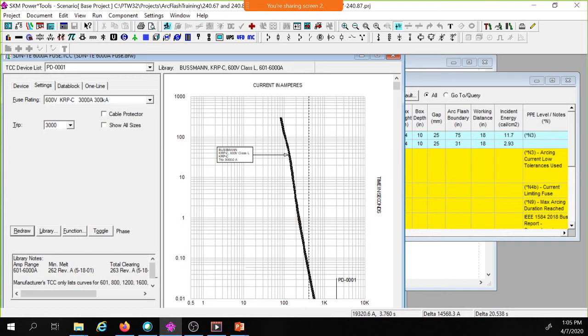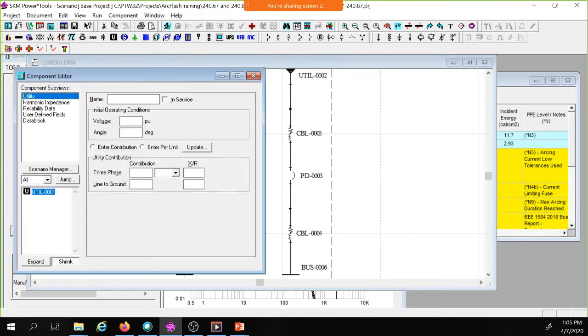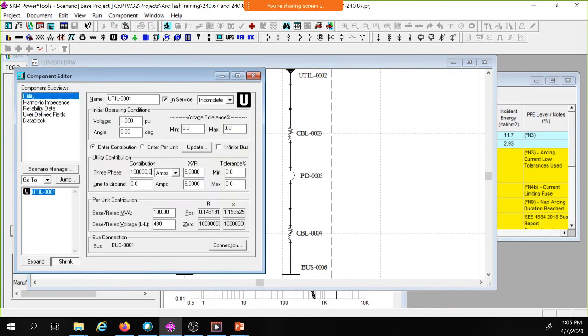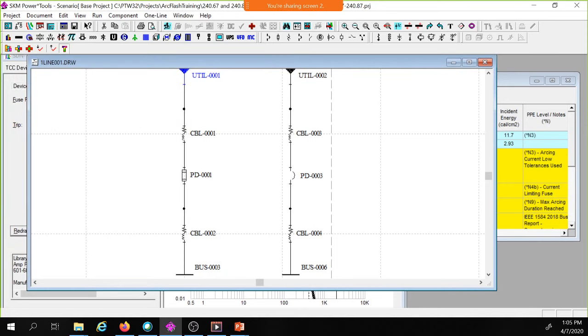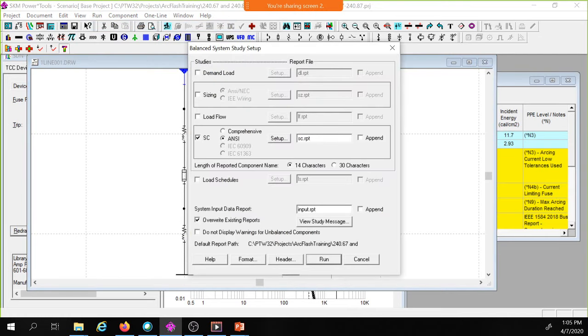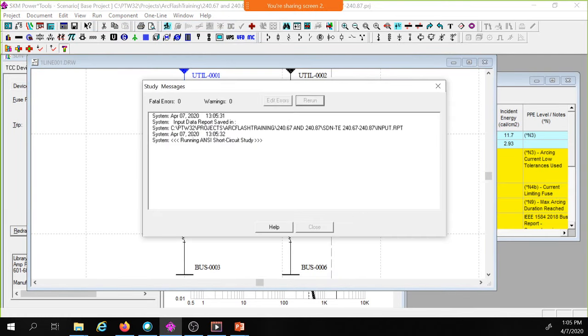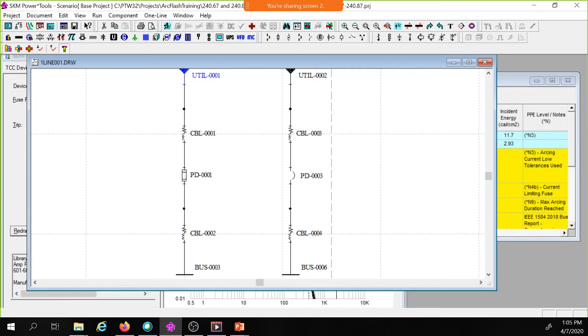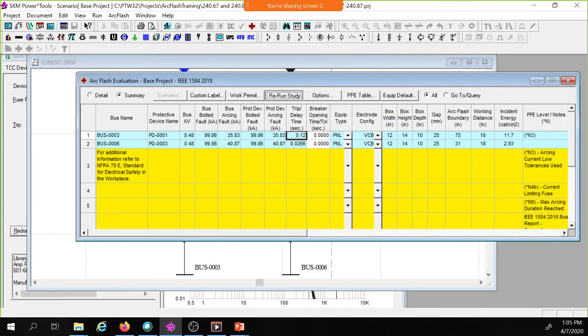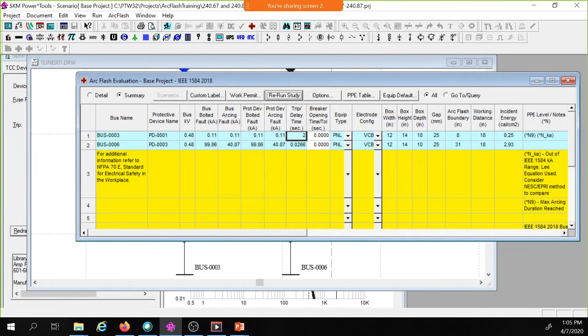So now I'm going to take this utility, and instead of 100,000 amps, I'm going to make it 106,000 amps. That's the limit. I'm going to run the ANSI short-circuit study. I recalculated my fault currents, and I'm going to rerun my flash study.